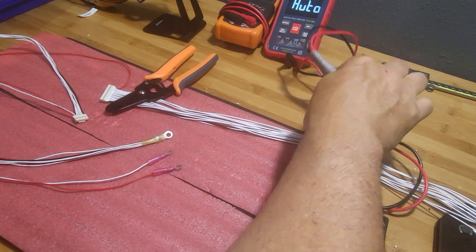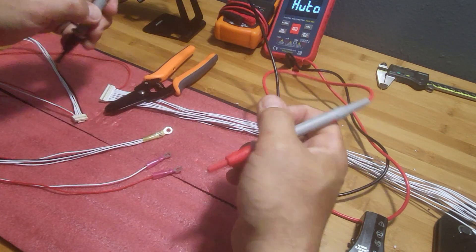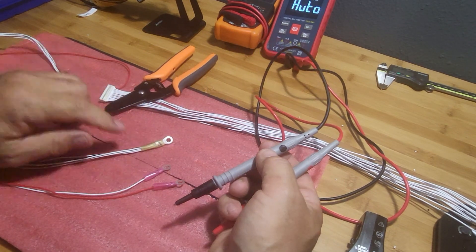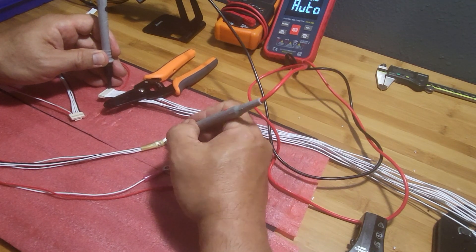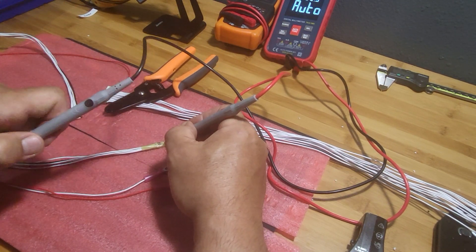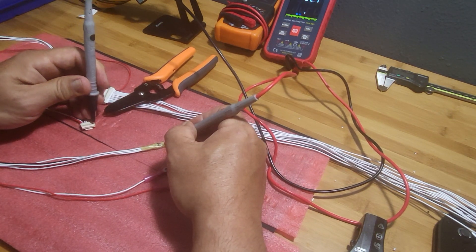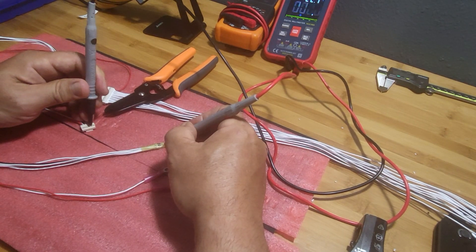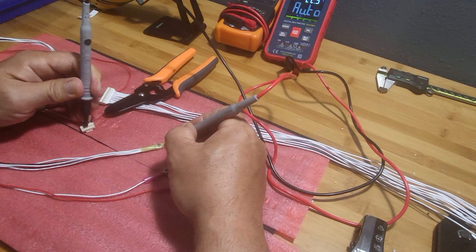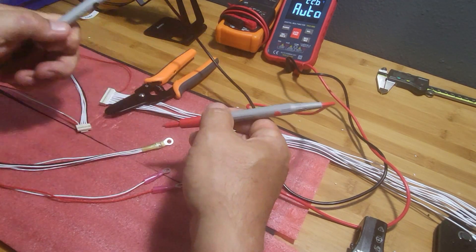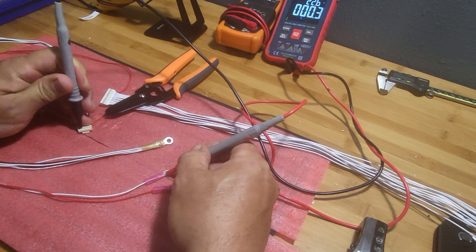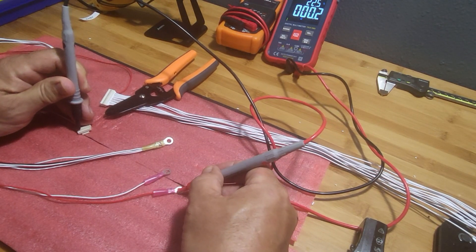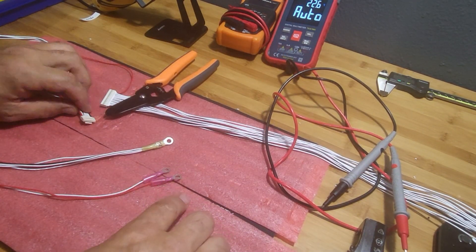All right, what I have here is the bundle for cell 14 and I have 15 and 16, and I want to check continuity. This bundle for 14 should have continuity from this lead here to the terminal, which it does. And then I should be able to stay on the terminal and go to my next set of bundles - first wire correct, second wire correct, third wire correct, fourth wire correct, and fifth wire correct. So I have the correct continuity between this bundle of six wires. Now I'll move over to the white wire which is number 15, and then I'll move over to the red wire which is number 16, and I'm good to go on these bundles.